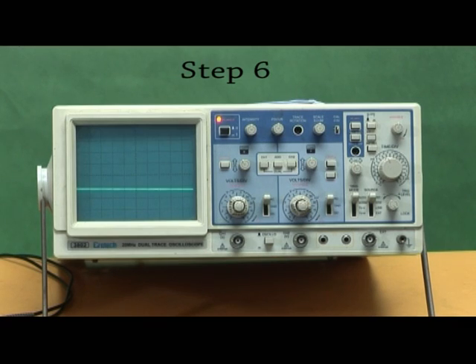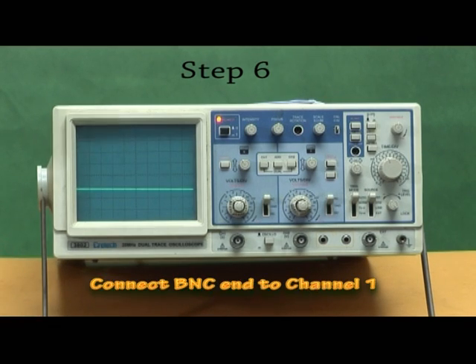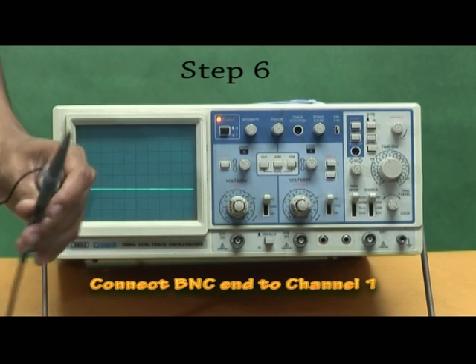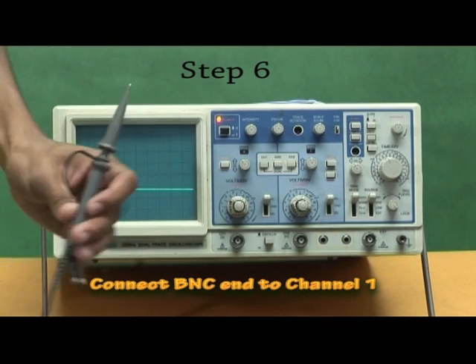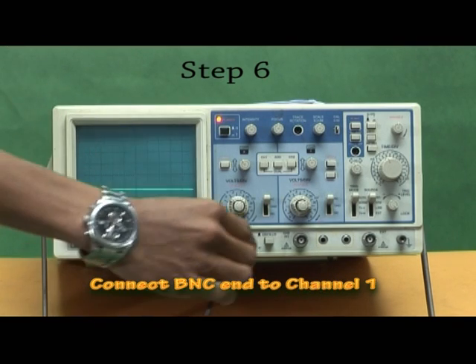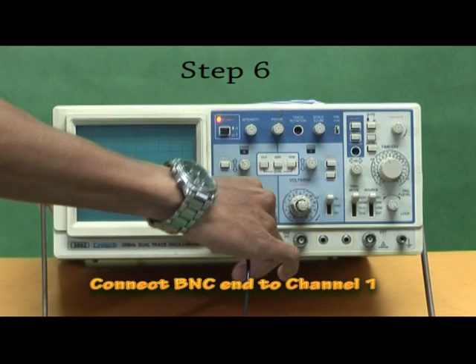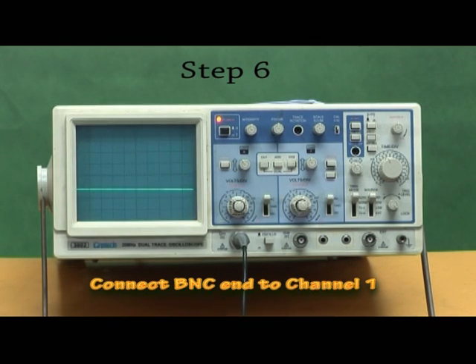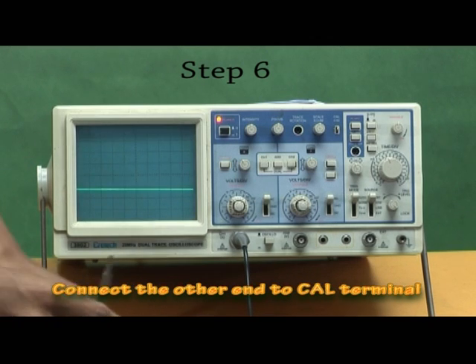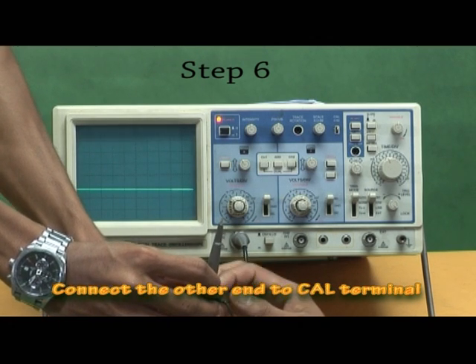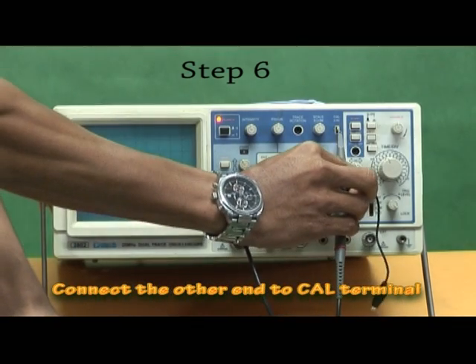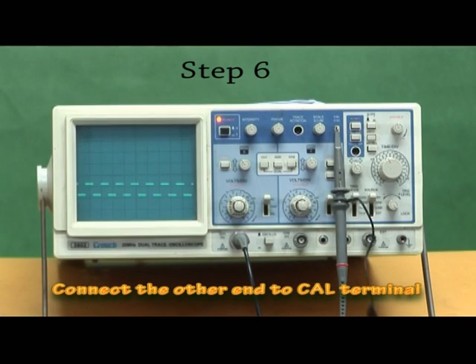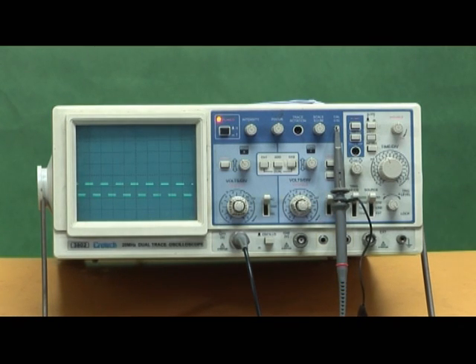Sixth step, connect the oscilloscope cable. Connect the free end of the BNC cable to channel 1 on the oscilloscope, and the other end to the calibration terminal. Push down on the top part to expose the little hook. It is not necessary to connect the ground lead of your test probe for calibration.